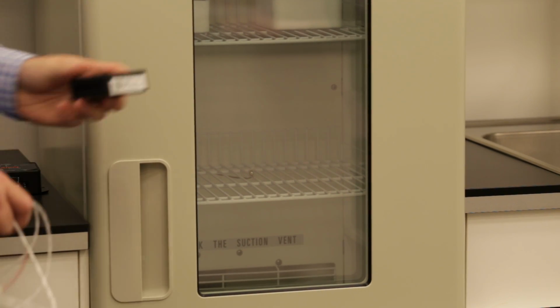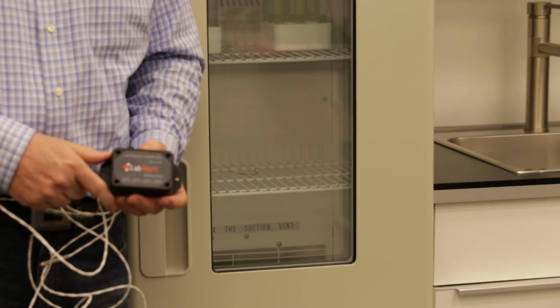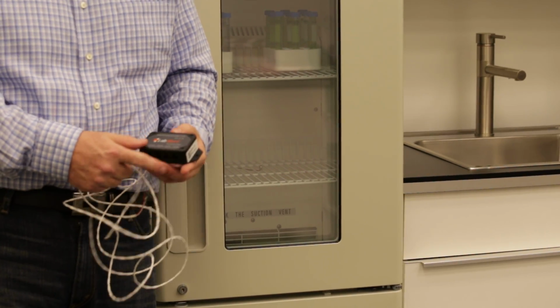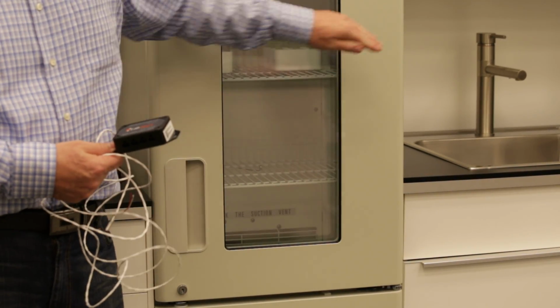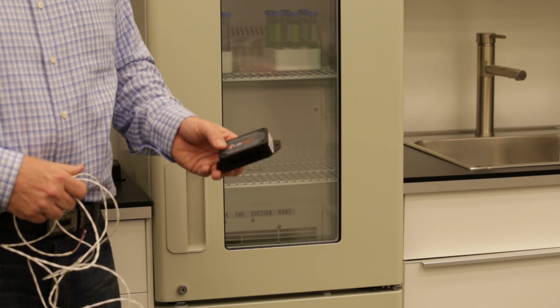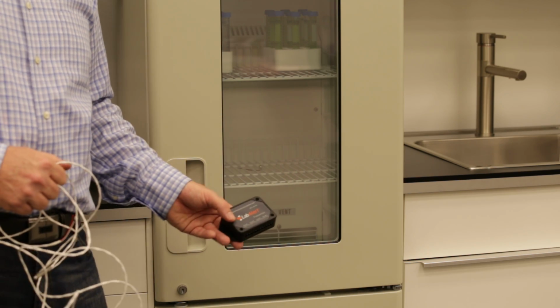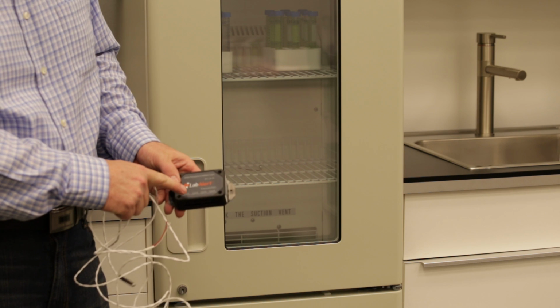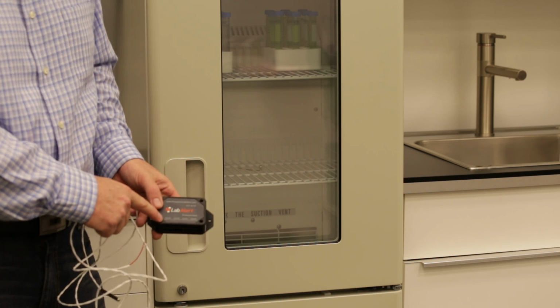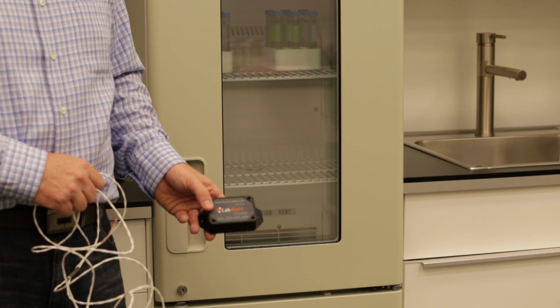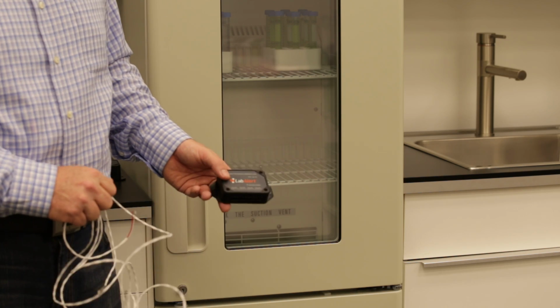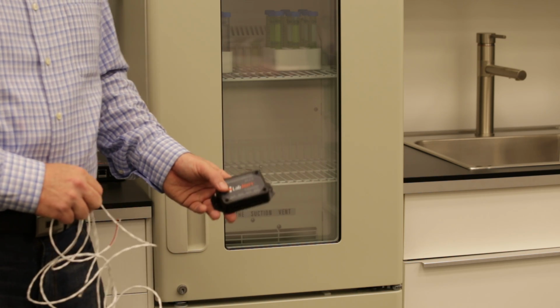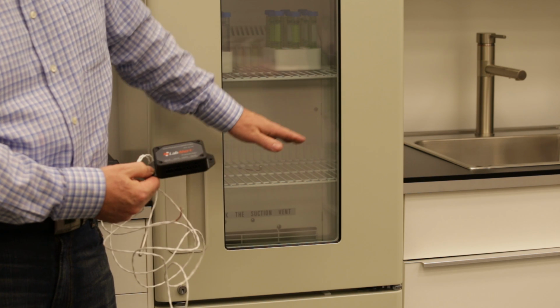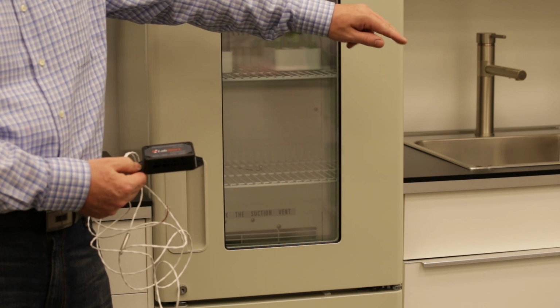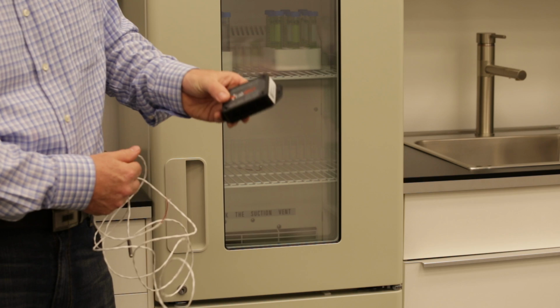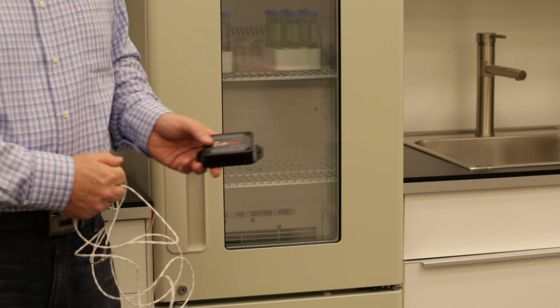So in this case, even though the transmitter will take up to 4 inputs, unless there is a piece of equipment very close by, we're going to want to use one transmitter for this 215 to take in both of the signals in temperature 1 and 2. So we can read the fridge temperature, we can read the freezer temperature, and tie them in to this one transmitter. If we had another piece of equipment right beside it, where we didn't have to run that cable probe more than 10 feet to where the transmitter is, then we would be able to add a third one.